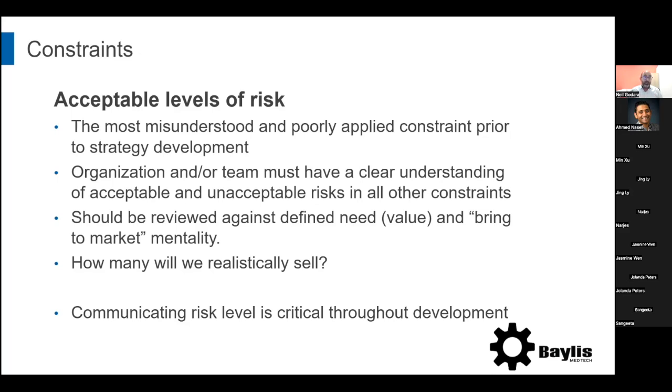It's happened to me where we've brought a product to market and we've said, hey, we got it done really quick. And then the doctors start using it and everything starts falling apart. I mean, we never design a product where the patient's going to get hurt, but the procedure's not as efficient as we thought, or the product doesn't have the efficiency we expected, or things like that. And you go back and look at it and say, okay, we had rose-colored glasses on. These things were identifiable earlier on in the process, and if we had worked a little bit harder, we probably could have fixed it. But now we've already released the product. To go back and change it and update the regulatory filings and all that is very difficult.